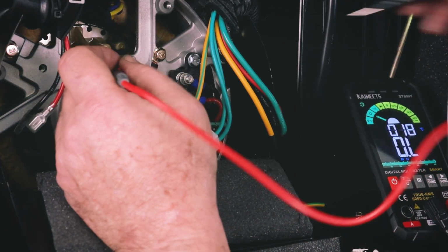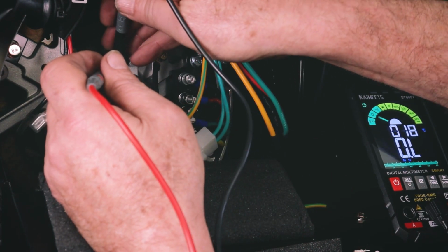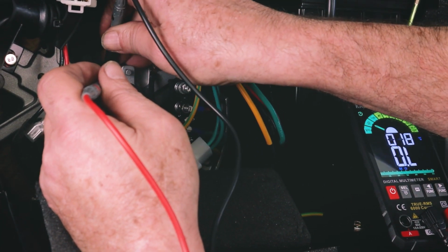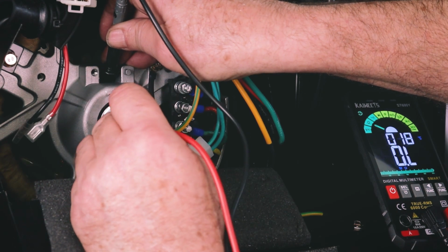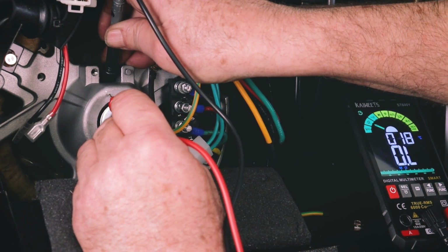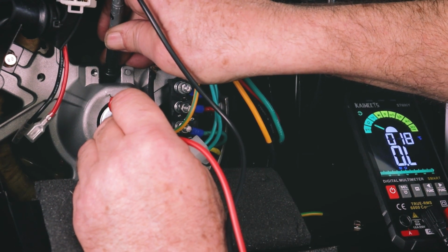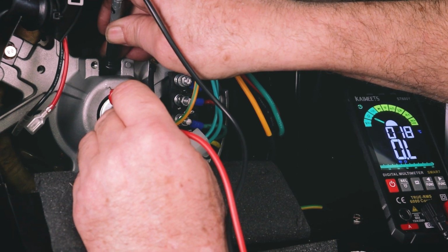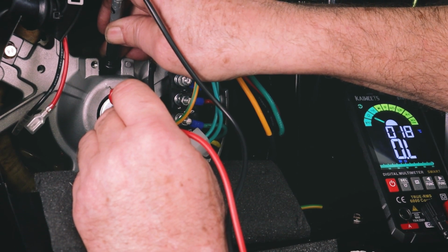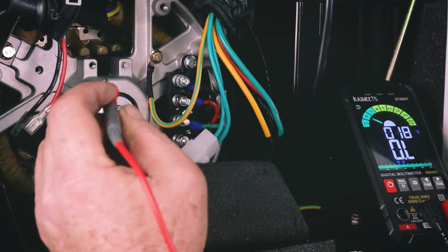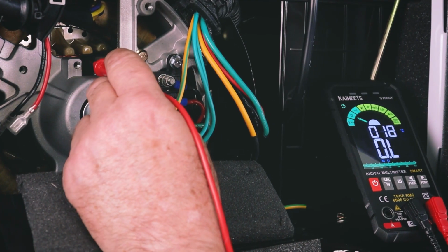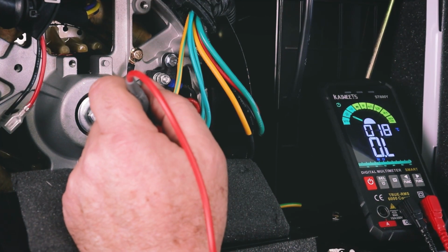Another thing you can do is go off the windings. Let's see if I can just touch on the rotor again and just touch the rotor to earth, and you'd be expecting, and I'm on one of the slip rings there, and again my meter says OL, oh well, that means it's completely insulated from ground, that means it's good. So that means we haven't got a breakdown in the windings there to ground on the machine.